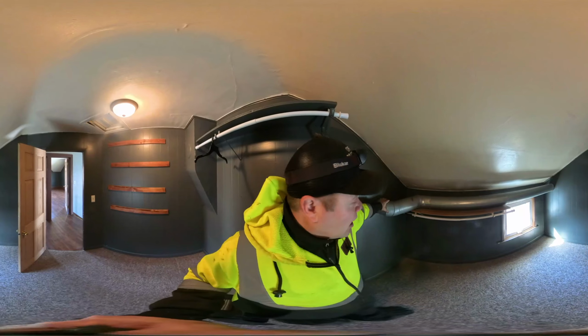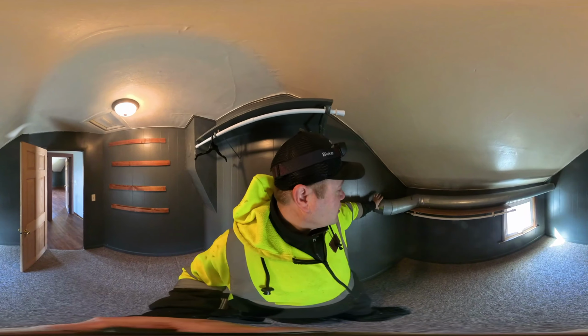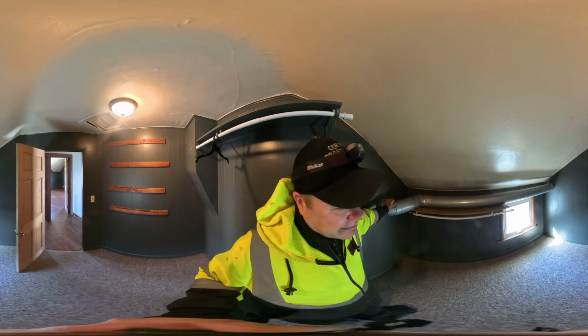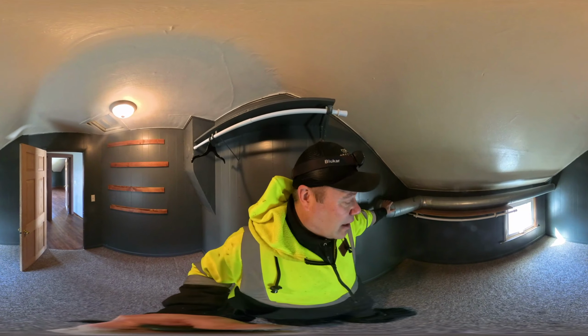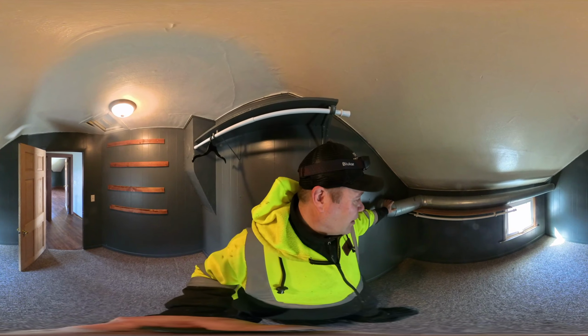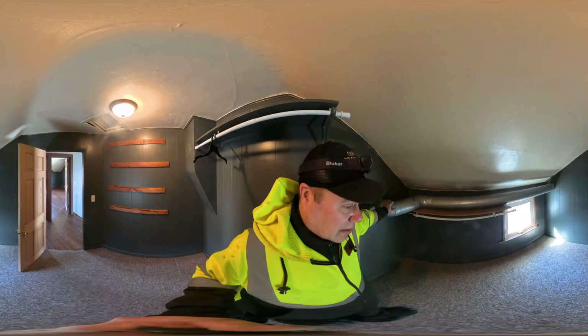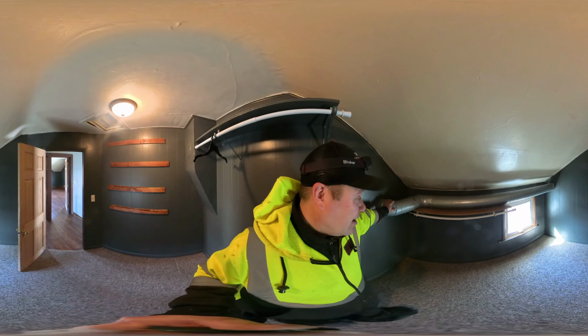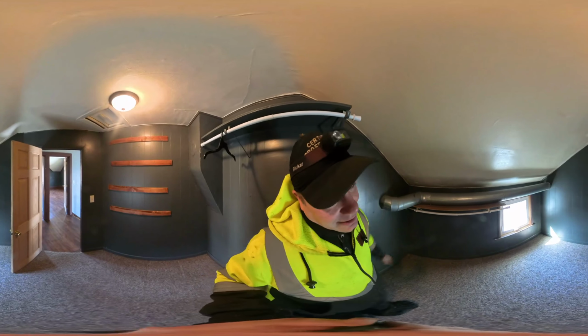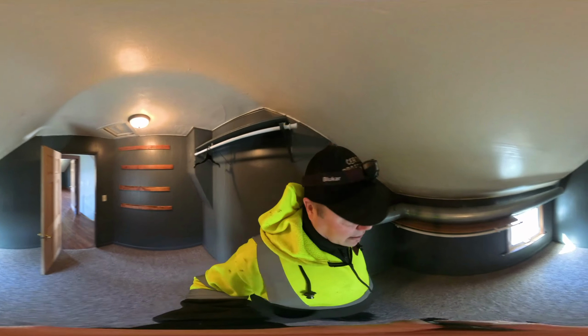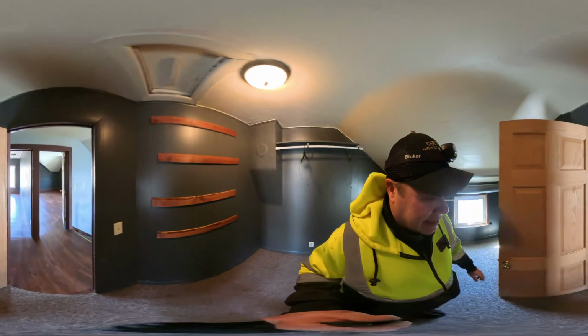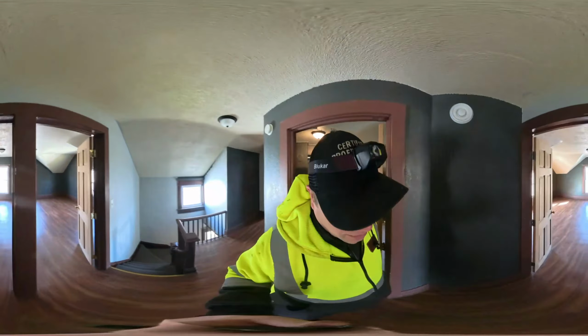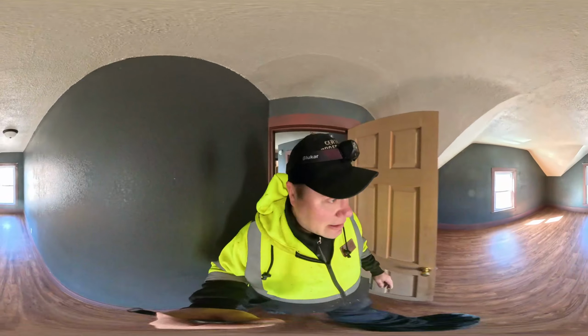So does this need to be 2 inches of combustible clearance all the way around? No. I mean, depending on who you talk to, but when I took my thermal imager to it with the heat on for a good half hour, this didn't get no hotter than 75 degrees up here. And down the basement it was pretty much the same, maybe 2 to 3 degrees hotter than upstairs.